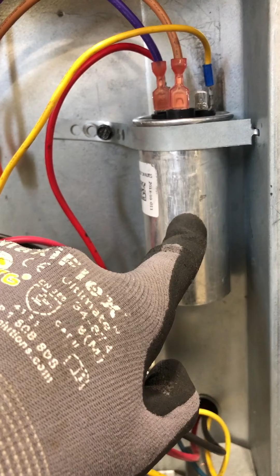This is the weakest link in the system. Heat beats these guys up, so the hotter it gets outside, the more of these fail. And when these fail, these motors can't start, the condenser and the compressor can't start. And if they do start, they run really hard. And sometimes, especially with the condenser fan, it will run the wrong direction if this capacitor has failed.